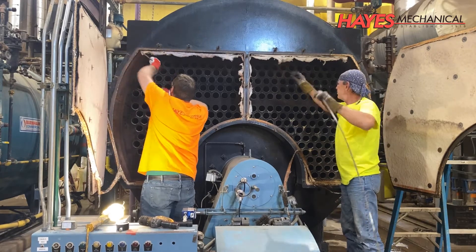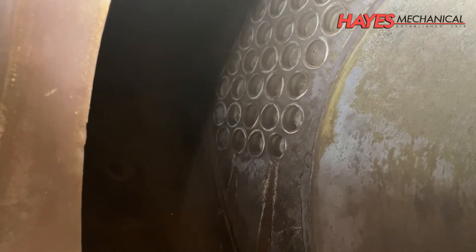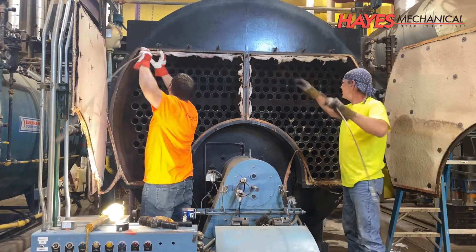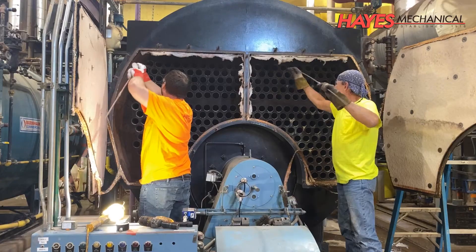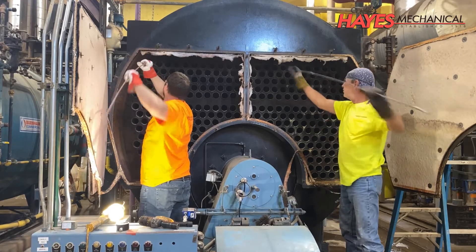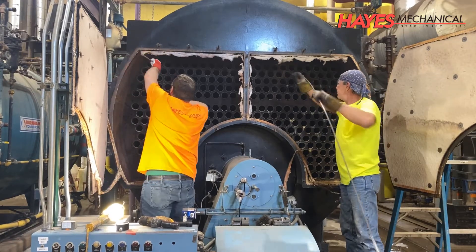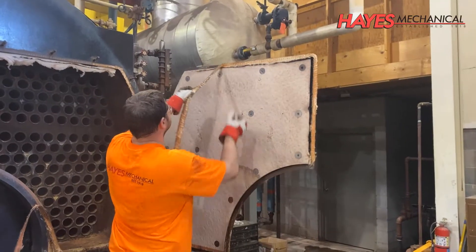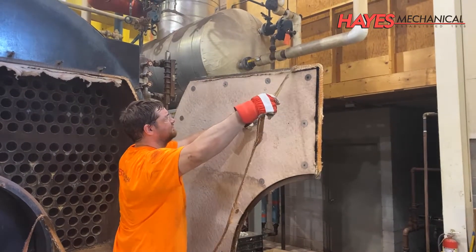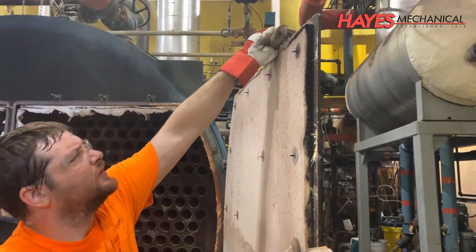In addition to reducing your boiler's efficiency, soot, when combined with moisture, will create sulfuric acid. This sulfuric acid will damage your tubes and eventually cause the tubes to fail. By cleaning the tubes manually with brushes rather than using a brush machine, our technicians are able to feel for any tube defects during the cleaning process. The fire side door gaskets are then removed and the surface is cleaned to allow for new gasketing to be installed when the doors are sealed.